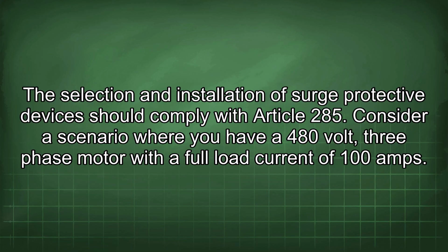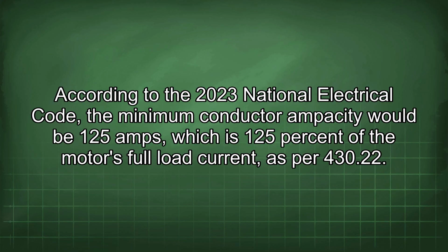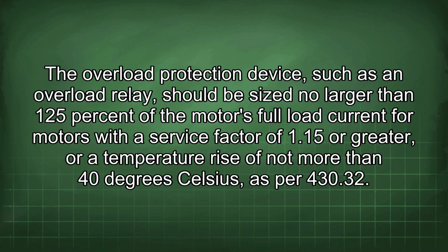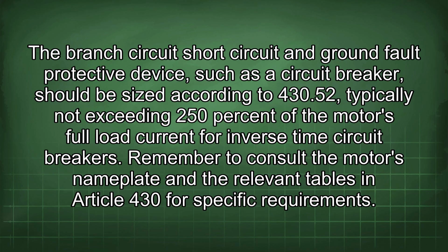Consider a scenario where you have a 480-volt, three-phase motor with a full load current of 100 amps. According to the 2023 National Electrical Code, the minimum conductor ampacity would be 125 amps, which is 125% of the motor's full load current, as per 430.22. The overload protection device, such as an overload relay, should be sized no larger than 125% of the motor's full load current for motors with a service factor of 1.15 or greater, or a temperature rise of not more than 40 degrees Celsius, as per 430.32. The branch circuit, short circuit, and ground fault protective device, such as a circuit breaker, should be sized according to 430.52, typically not exceeding 250% of the motor's full load current for inverse time circuit breakers. Remember to consult the motor's nameplate and the relevant tables in Article 430 for specific requirements.